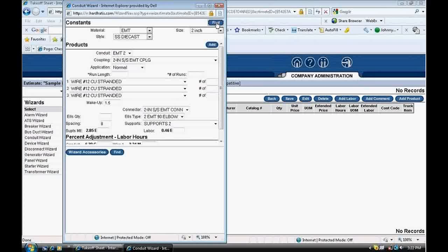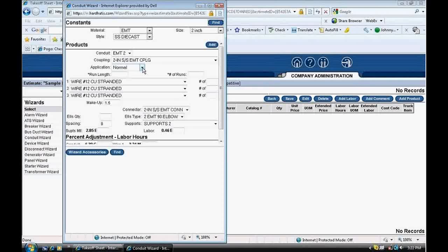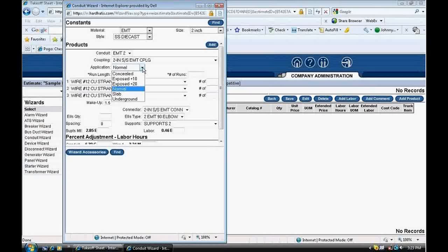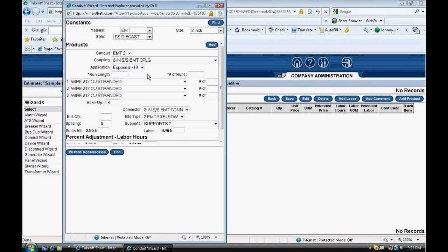As discussed earlier, the term conduit application refers to the conduit installation levels of difficulty. Red Rhino has several conduit applications. Each application has different labor quantities depending on difficulty of installation. As shown on the takeoff sheet, I set the application at plus 10 feet, like the conduits to be installed above 10 feet off the floor. If the conduit run were 20 feet from the floor, I would have selected 20 feet. Again, applications refer to the level of difficulty of the conduit run, and the program has more labor built in for more difficult runs.